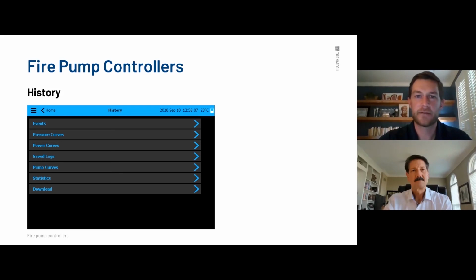Once it gets past that 500 events, everything gets archived into this saved log section. And the neat thing about the saved logs is that you can actually go in and look by date, by month, by year. It's keeping track of a lifetime of events of this control panel. So if you know you had something that happened in, say, July, you can go back into the saved logs, sort just by that date, and narrow down exactly what you're looking for. It helps find an issue in a system a lot more efficiently than trying to scroll through a whole database of events. So that's what the date and timestamp is really good for.